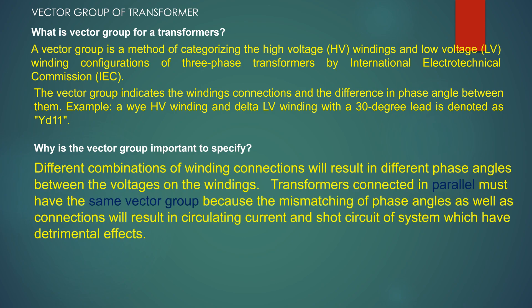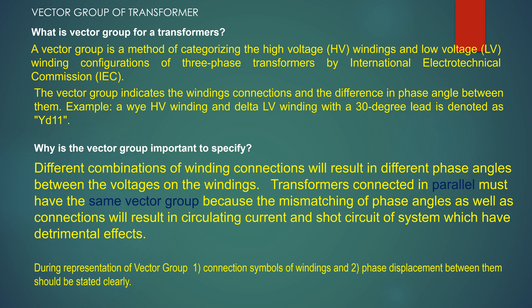Different combinations of winding connections will result in different phase angles between the voltages on the windings. Transformers connected in parallel must have the same vector group, because mismatching of phase angle as well as connections will result in circulating current and short circuit of the system, which have detrimental effects. During representation of the vector group, the connection symbol of windings and the phase displacement between them should be stated clearly.